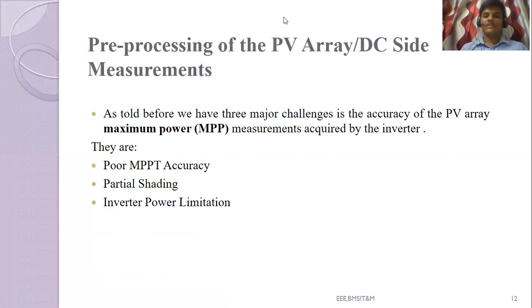As we move on, one more thing for checking is pre-processing of PV array or DC side measurements. As told before, there are three major challenges in the accuracy of the PV array maximum power point, MPP: poor MPPT accuracy, partial shading, and inverter power limitation. Initially, we'll discuss poor MPPT accuracy. It is an issue that can arise when inverter measurements have low accuracy in measuring the PV array maximum power, due to poor MPP tracking, that is the MPPT of the inverter, in fast changing irradiance conditions.